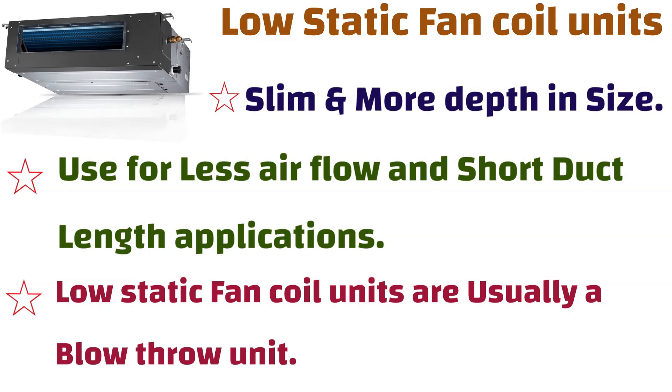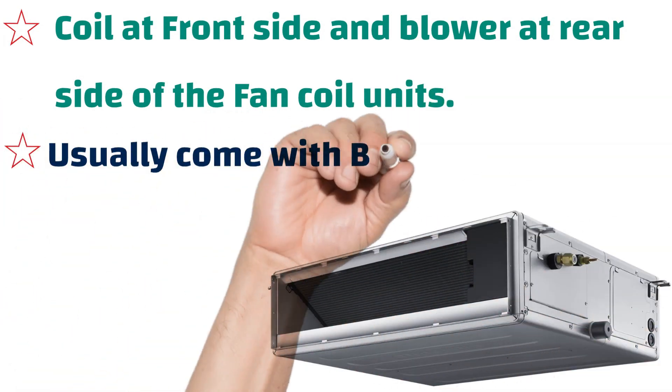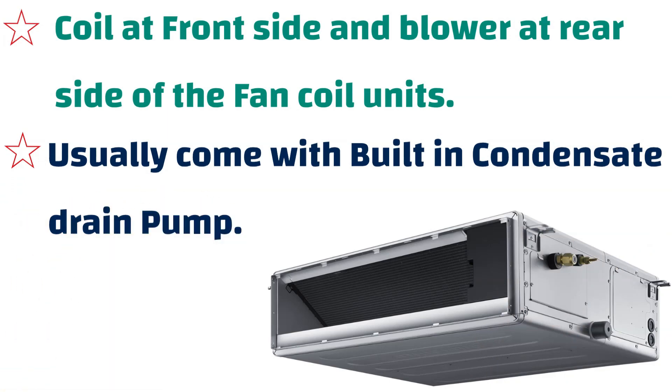Three, low static fan coil units are usually a blow-through unit. Four, coil at front side and the blower at rear side of the fan coil units. Five, usually come with built-in condensate drain pump.